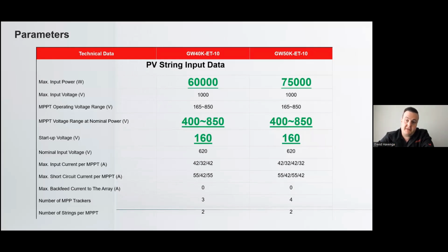The operating voltage is also quite wide on these units, 165 to 850 volts, where the nominal range is 400 volts to 850 volts. So the ET can also be used as purely an on-grid inverter as well. You can put PV on it and batteries on it just for self-consumption. You can even use it just for self-consumption, even without batteries. Then our nominal voltage will have to be higher, as in the 400 volts.